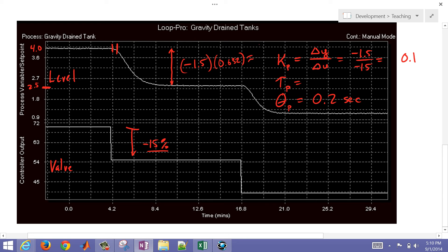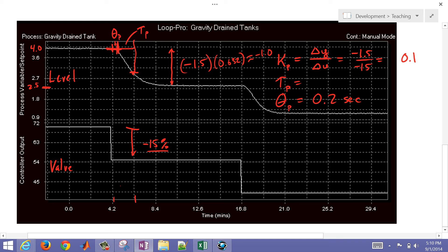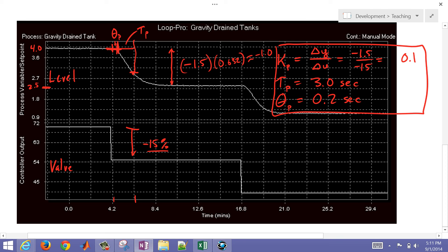So if I just multiply this by 0.632, that's approximately just a little bit less than negative 1. So I look to see where it started, and then it's going to be negative 1 right around 3, about right here. And then this was the dead time. And then this amount of time is going to be the time constant after the dead time. So the time constant, let's just say from here to here, that's going to be about 3 seconds. So we have a gain of 0.1, a time constant of 3, and then an apparent dead time of 0.2.